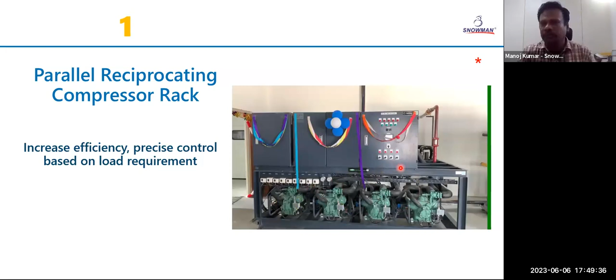Another good thing we have done since the beginning: 43 warehouses constructed over a period of 25 years. The first warehouse we constructed, in 96 or 97, also had compressor rack systems and hot gas defrosting. Hot gas defrosting is really mandatory for such warehousing operations, because when the door is open, a big volume of air enters, and because of that volume, ice formation is quite high. So it won't be effective if you put on heaters or something like that. It's a complete study we made, and we have been doing hot gas defrost.